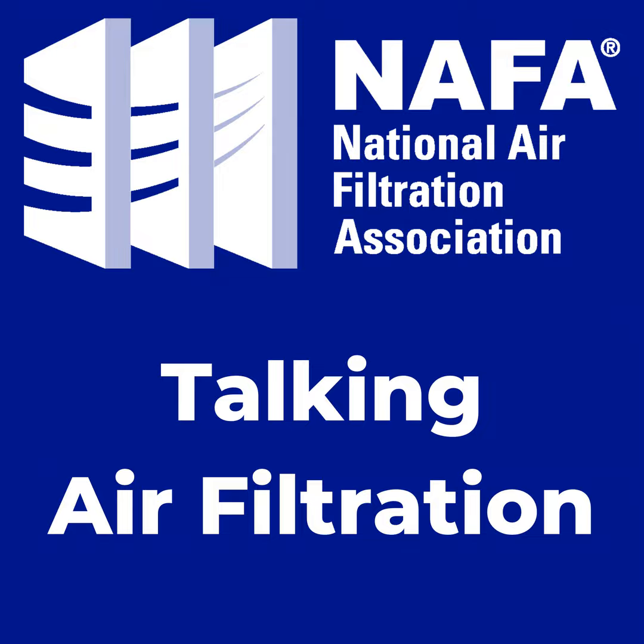So looking at comparing a traditional box style HEPA or the supply panel style HEPAs, as we call them, for clean rooms, you can see here for the 11.5-inch deep filters, looking at the microglass, you got about an initial resistance of 1 inch at the rated airflow velocity. And for the PTFE filter, the same configuration, you have about 0.56 inches, so almost half of the pressure drop. And looking at the media pressure drop versus the filter pressure drop, you can see that the difference is really coming from the media because the configuration is the same for the filters. So for the actual whole filter, 1.45 initial versus 0.7, and for the panel supply style HEPAs, you used to have a 0.53 inch initial resistance versus 0.27.